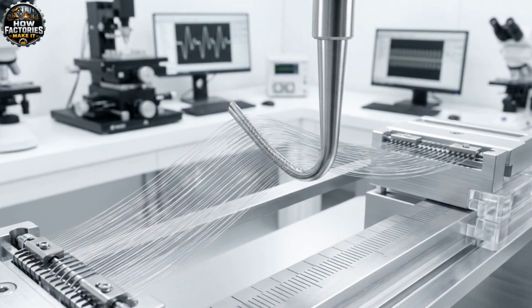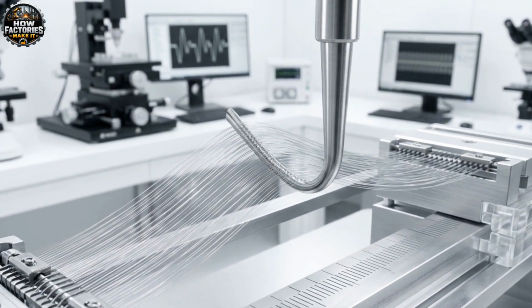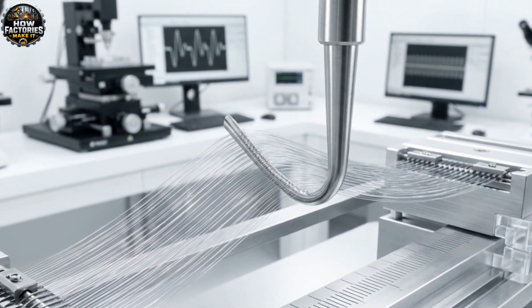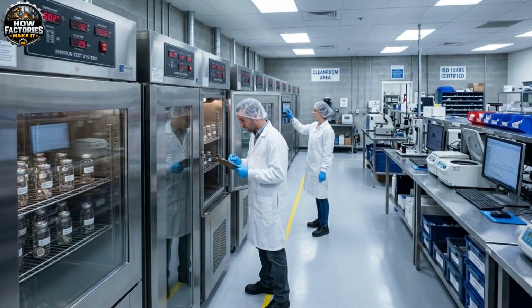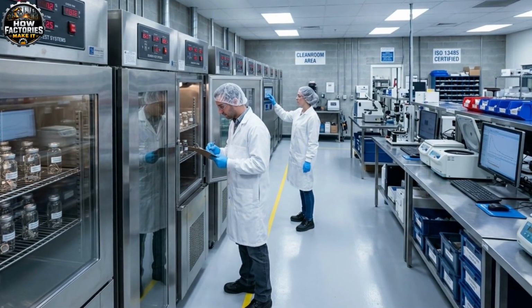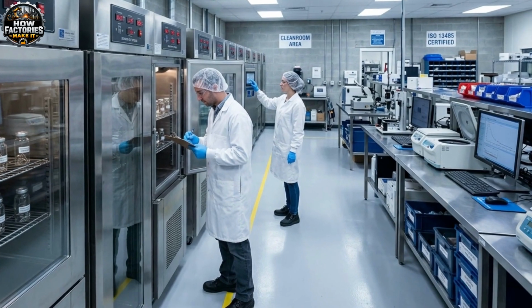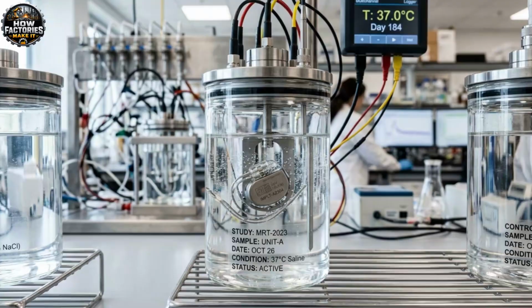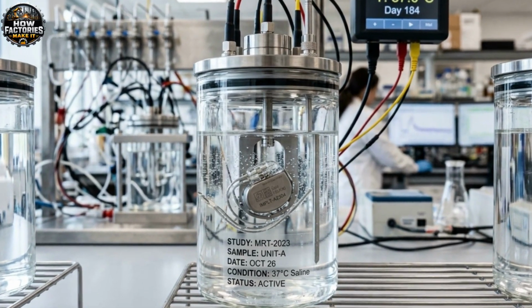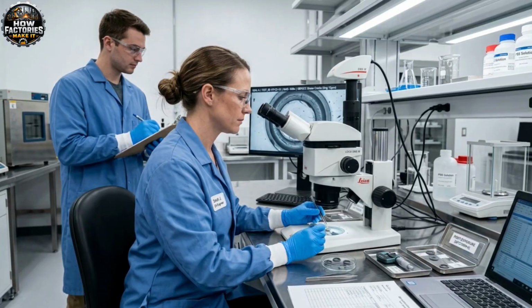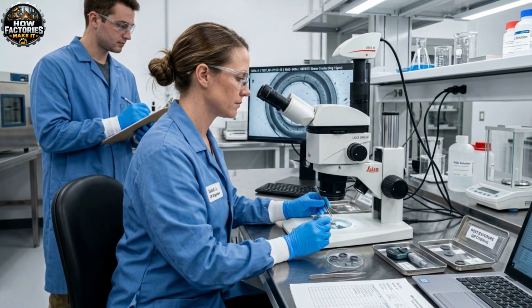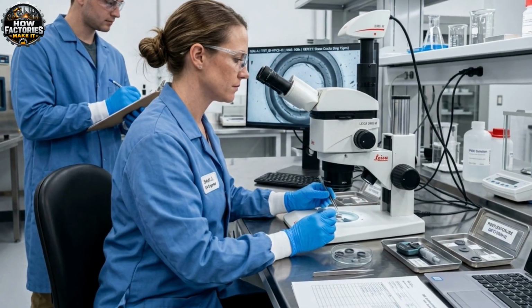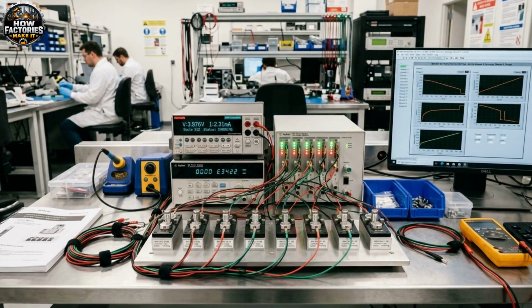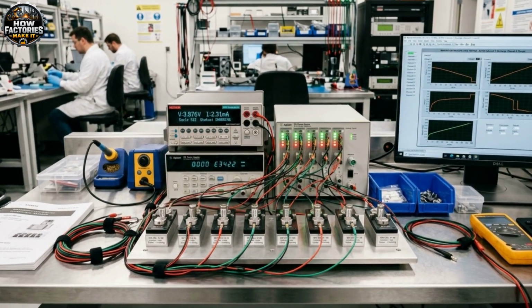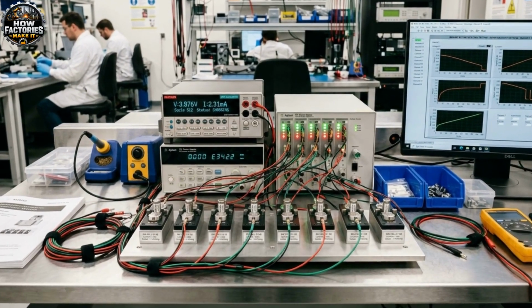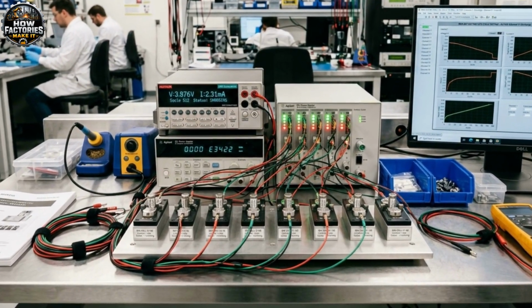Accelerated aging chambers expose test devices to elevated temperatures and controlled solutions. This helps engineers estimate how the materials and seals may behave after extended implantation. The battery is repeatedly charged and discharged. Wireless communication is tested under different positions and levels of interference. The implant must also continue operating safely if an electrode fails, communication is interrupted, or the battery reaches a low charge.